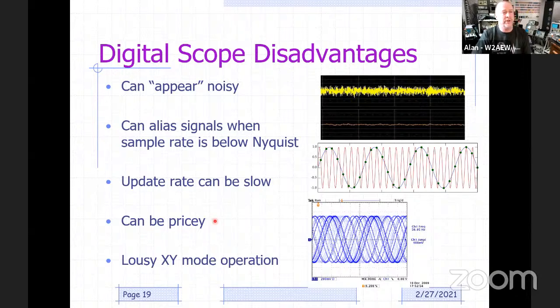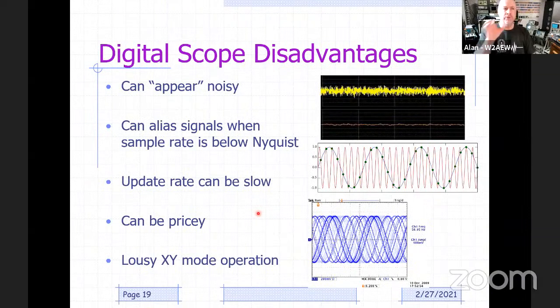And if you ever use XY mode, and we'll talk a little bit about XY mode later, the XY mode on digital scopes is generally pretty lousy compared to analog scopes, where it's actually pretty good. Okay, so that's probably all we're going to talk about in terms of the digital scopes themselves and their features, because the controls are very much the same. You still have the same vertical controls, same coupling controls. Horizontal is just called scale instead of sweep speed, but it's still calibrated in so many seconds per division. And the trigger controls are virtually the same, except like I said, there are a lot more triggers available to you, but as hobbyists, we're generally just going to use an edge trigger.